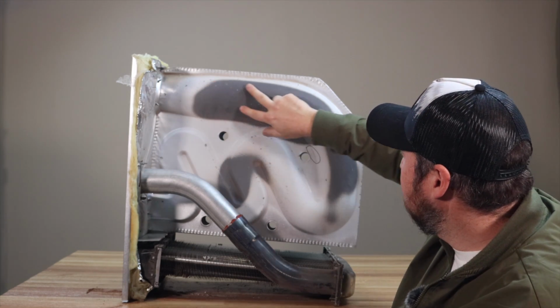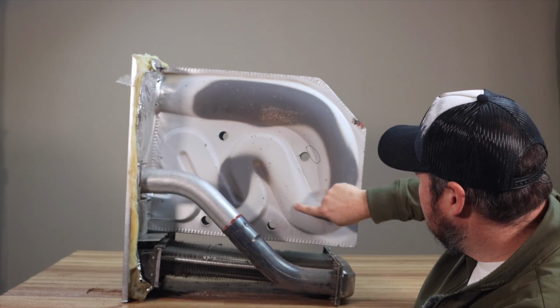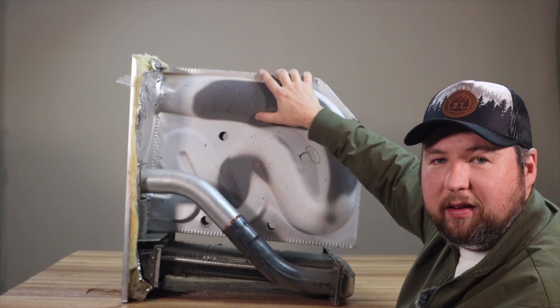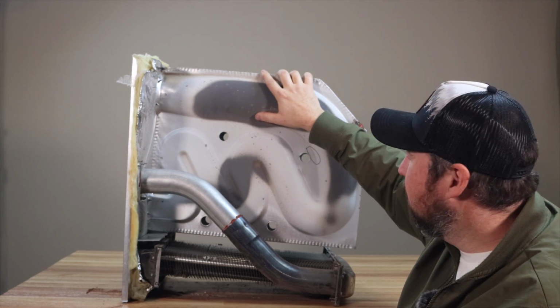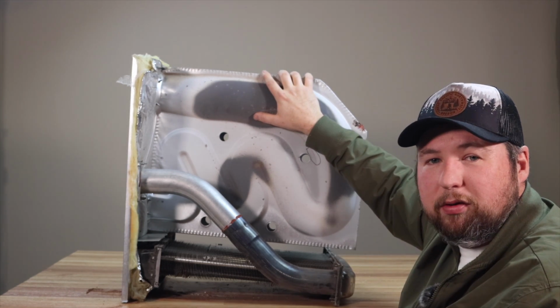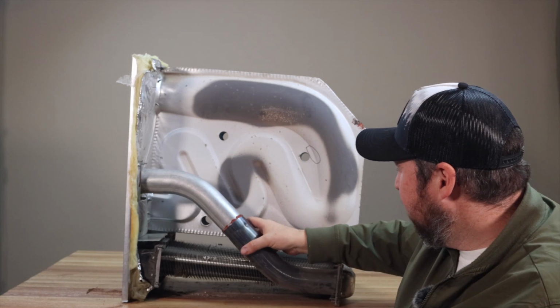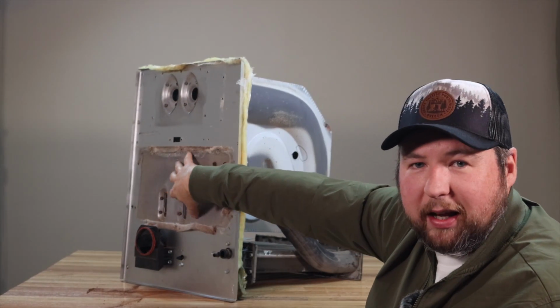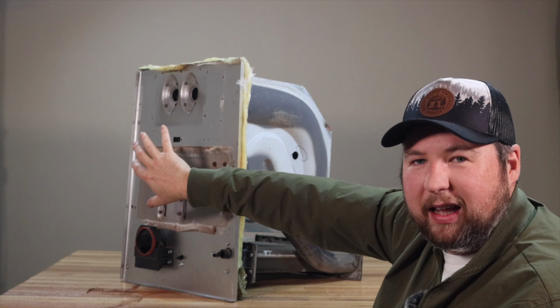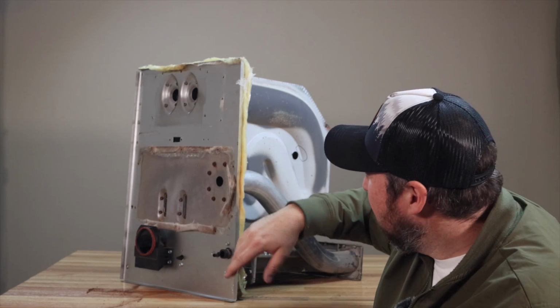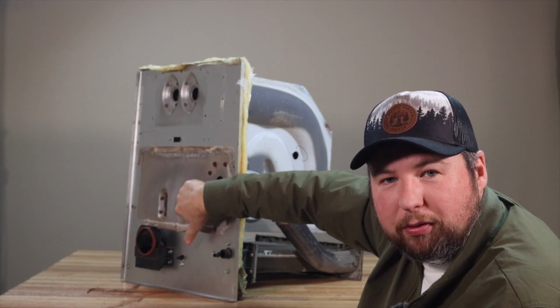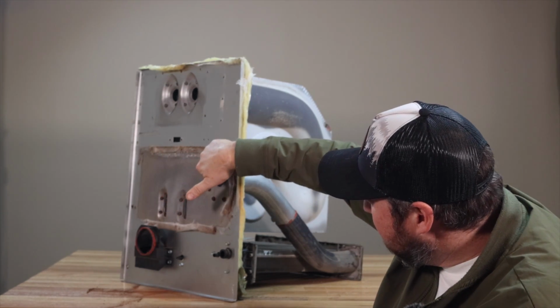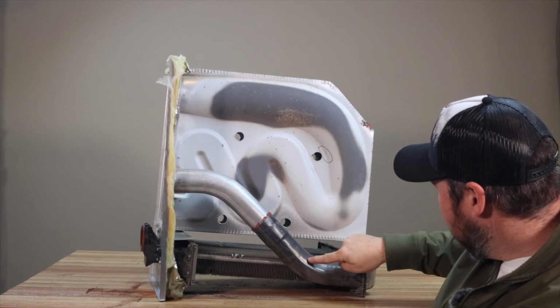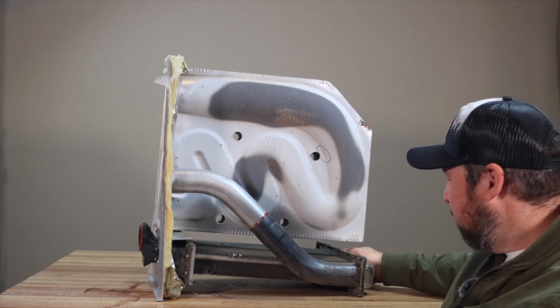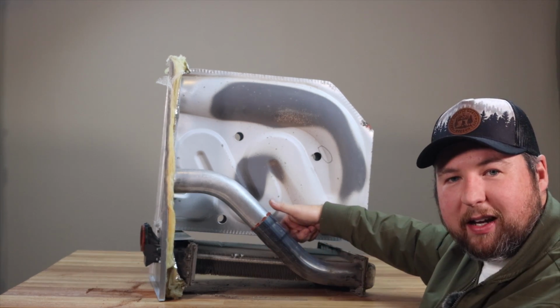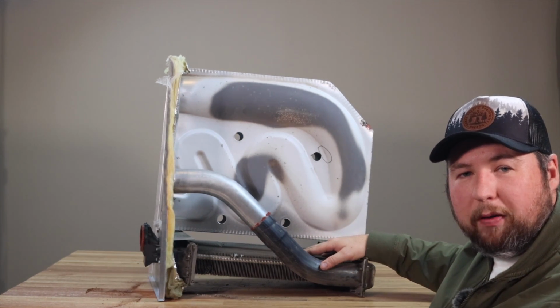So basically your burner's here, this is your combustion chamber, right? And it's going to snake through. Now this top heat exchanger here is what's called the primary heat exchanger, okay? So it's the standard heat exchanger just like you're used to on an 80%er. But on this particular one, there's a collection box right here on the front. You've probably seen it, it's got a bunch of insulation, a white insulation thing over it. And basically that heat's going to come out of these holes right here, and it's going to fill up that box and then go through this hole, which takes it through this tube, into this transfer box down here at the bottom, which is made out of stainless steel. And then it goes into these little tiny tubes at the bottom, which is what you call the secondary heat exchanger.